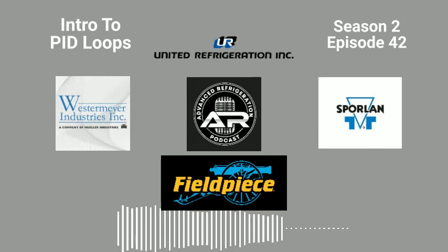And remember, the integral control senses the actual deviation of the actual evaporator, like if we're talking about evaporator superheat, from the actual set point. This way you can have that thing react the way you need. And so, basically Kevin's saying, start off with a very, very simple deviation of set point, with the P first. Am I correct in saying that?